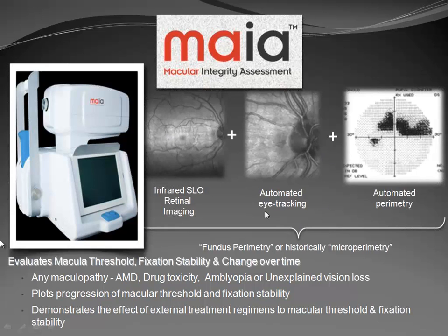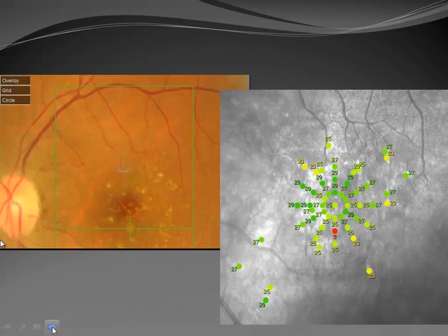And that's an automated eye track, and it allows us to always put the stimulus in the appropriate place, because we know precisely where the vessels are, we know precisely where the eye is, it's tracking the eye, and we can actually do reproducibility studies of separate points and show that it can always stimulate the point you want to stimulate. You can also go back and test the patient a week later, a month later, a year later, and you can test the exact same points again.